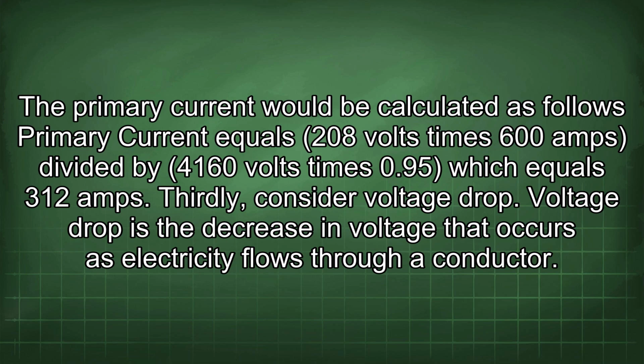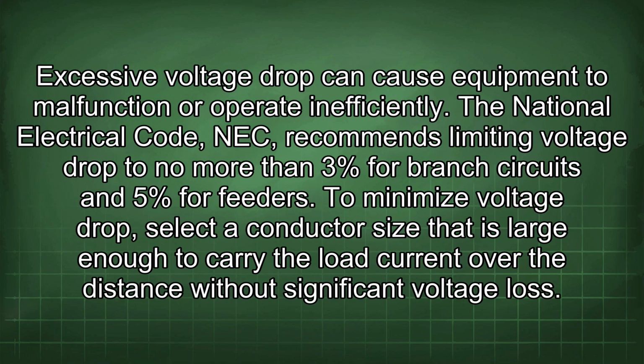Thirdly, consider voltage drop. Voltage drop is the decrease in voltage that occurs as electricity flows through a conductor. Excessive voltage drop can cause equipment to malfunction or operate inefficiently. The National Electrical Code (NEC) recommends limiting voltage drop to no more than 3% for branch circuits and 5% for feeders. To minimize voltage drop, select a conductor size that is large enough to carry the load current over the distance without significant voltage loss.